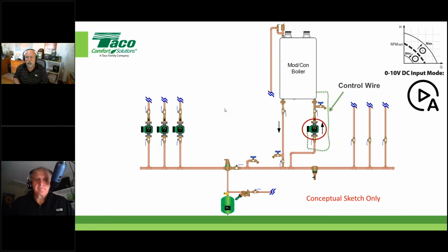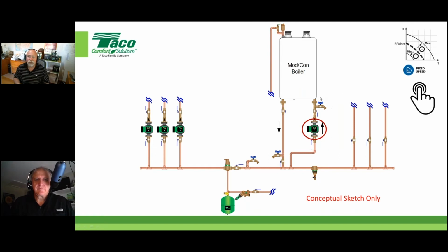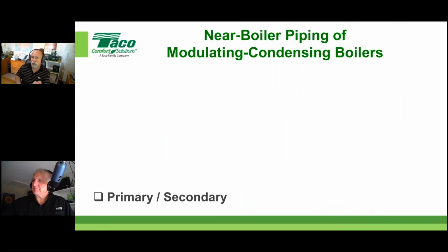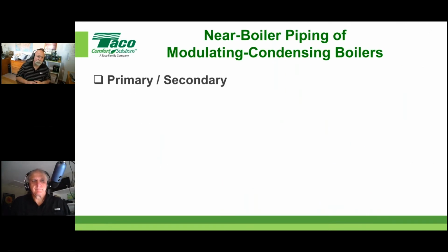Now let's focus on that same configuration when we don't have that control wire and all we're doing is banging this circulator on and off with a relay through this boiler. What I'm pointing out is the fixed speed mode of application for that circulator is what you want to be focused on, and that's what we're going to use in our sizing exercise. So just reinforcing this whole primary secondary thing, because again, most of the boiler manufacturers will tend to show you this, not all of them. So let me make this point very clear.